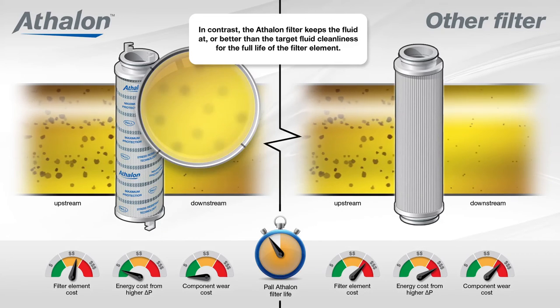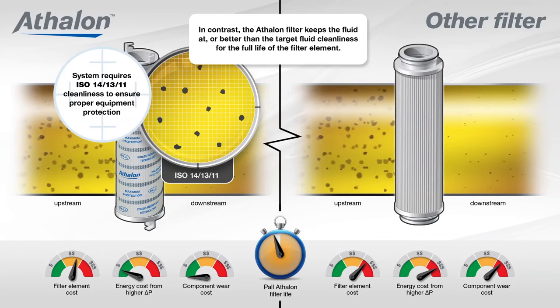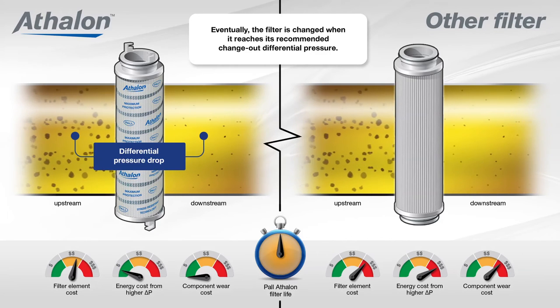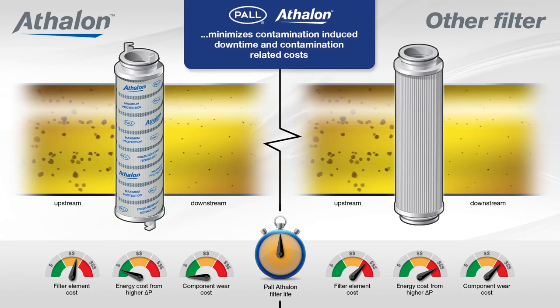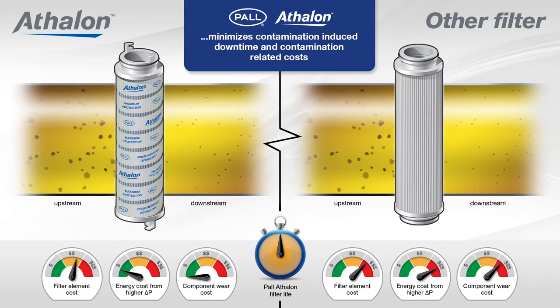In contrast, the Athalon filter keeps the fluid at or better than the target fluid cleanliness for the full life of the filter element. Eventually, the filter is changed when it reaches its recommended change-out differential pressure. By maintaining levels of cleanliness performance, Pall Athalon filters minimize contamination-induced downtime and contamination-related costs.